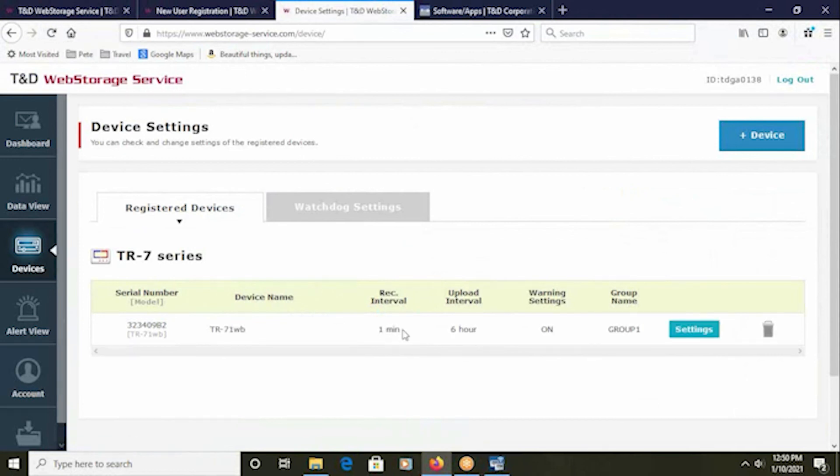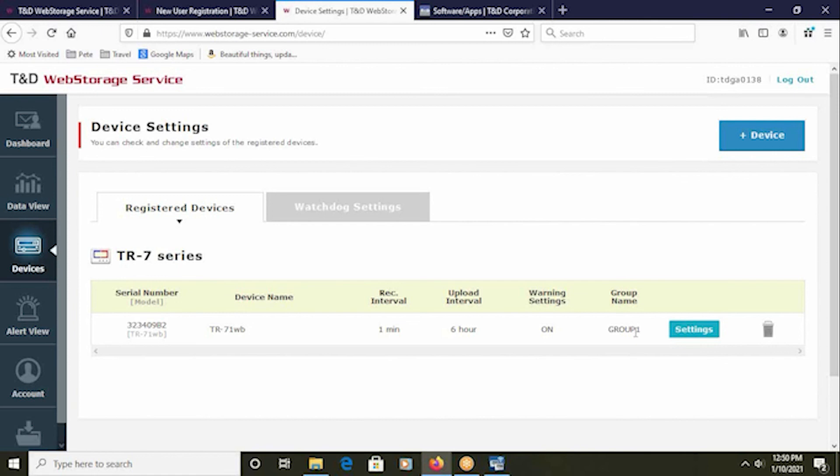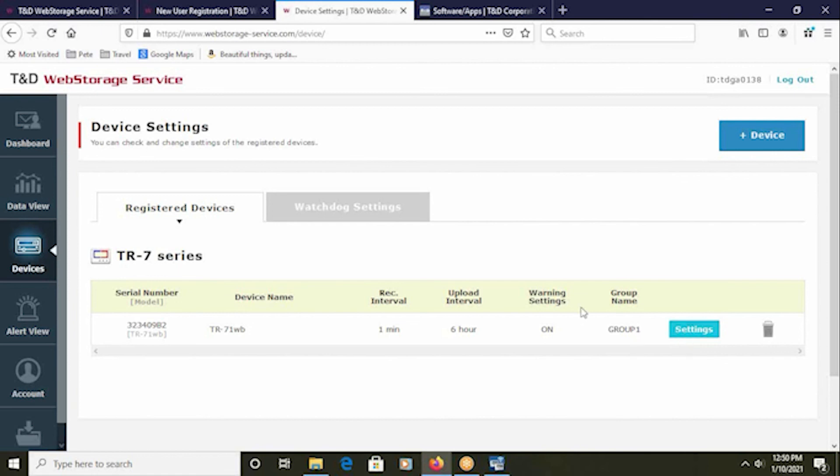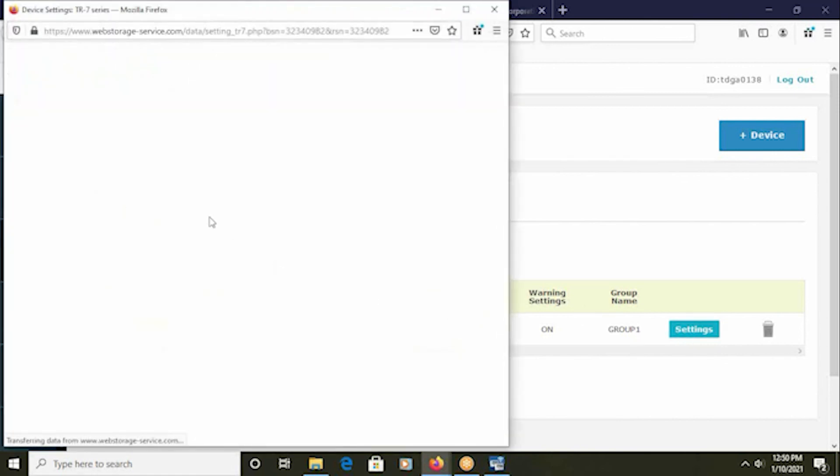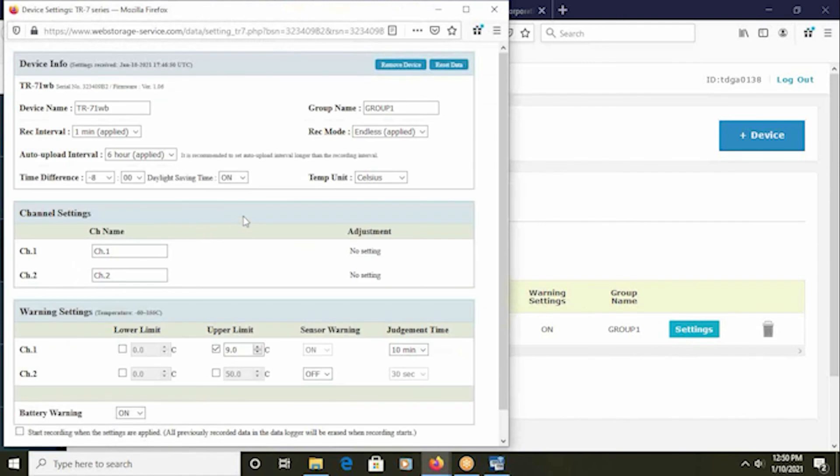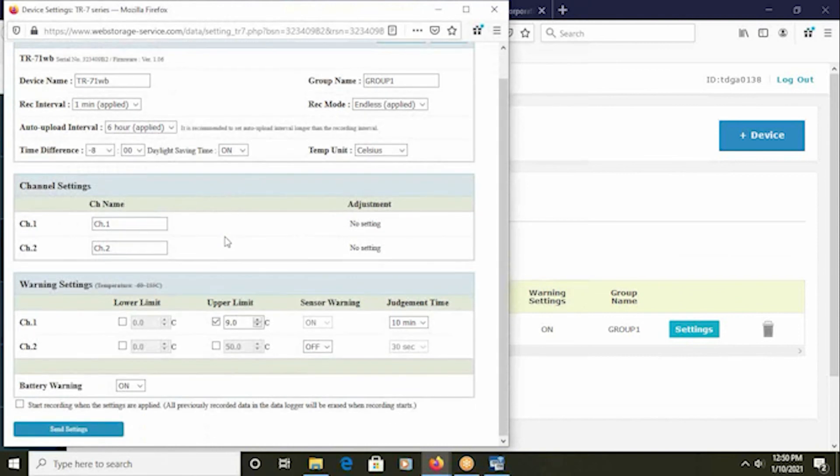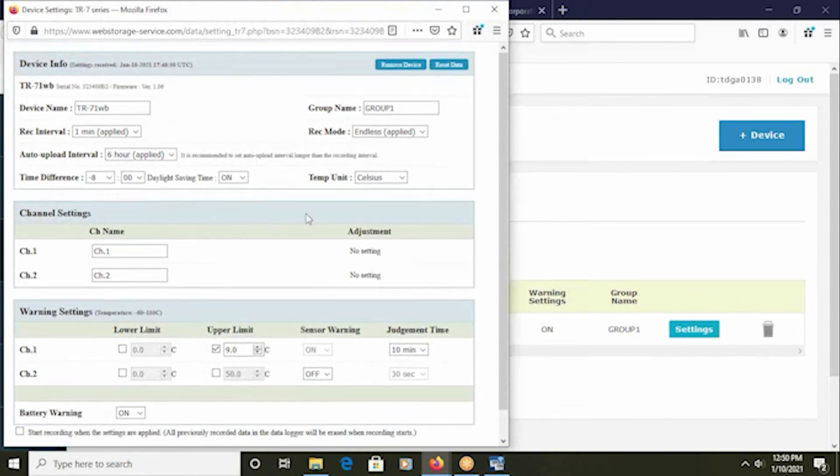There, my recording interval one minute. The upload interval was left at six hours with warning settings on and the group name of group one. Most of these settings, names, and intervals can be changed directly from the web storage service and not require the local software. This concludes the video.